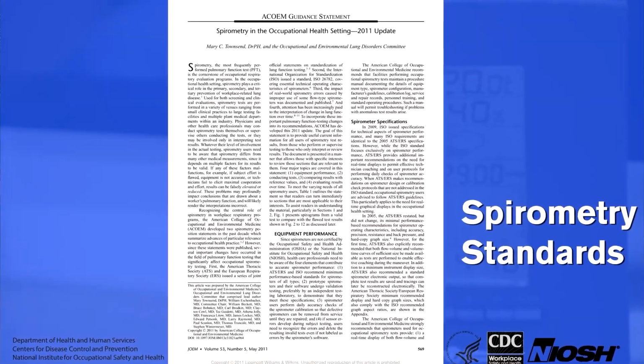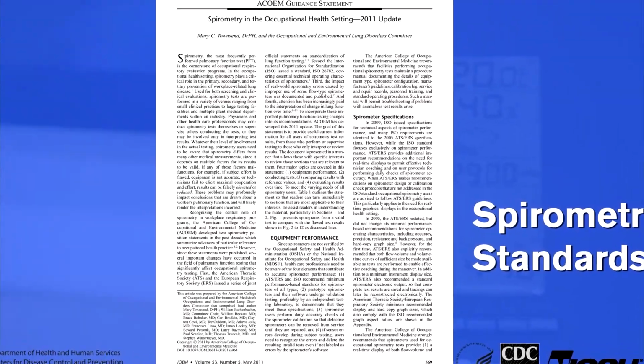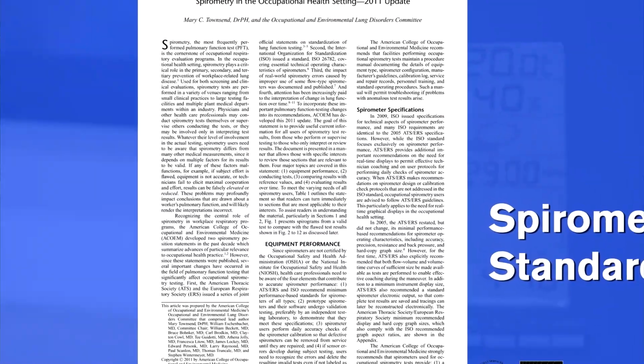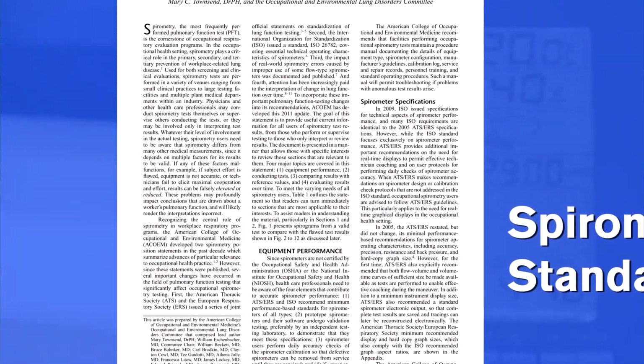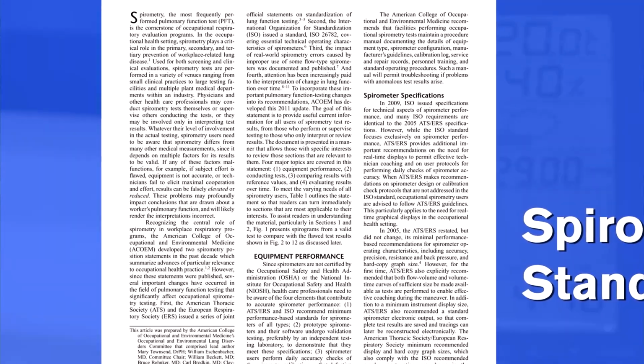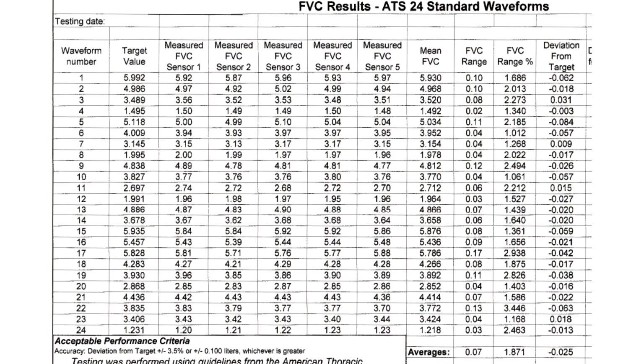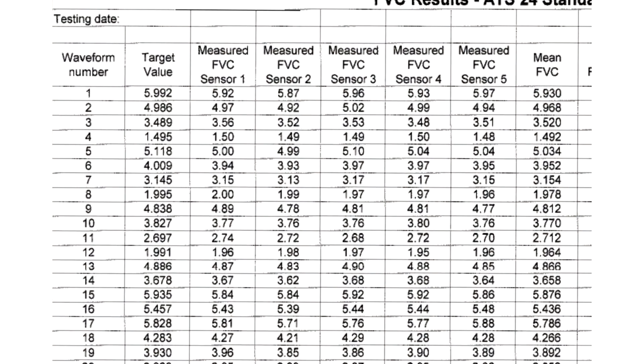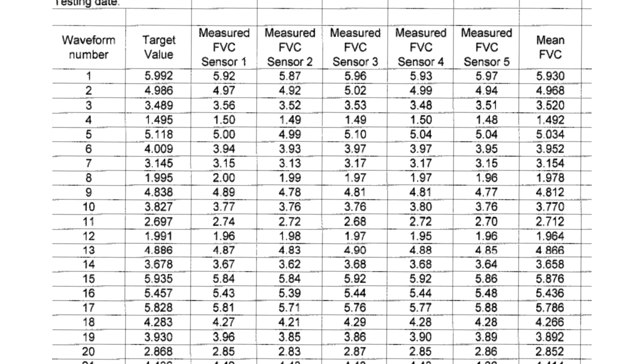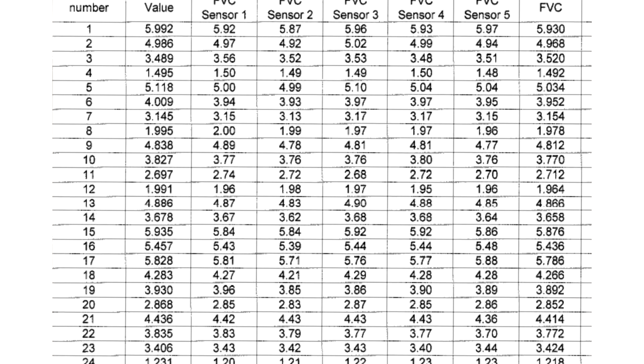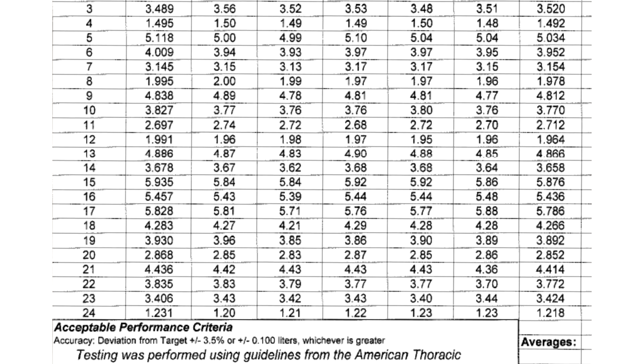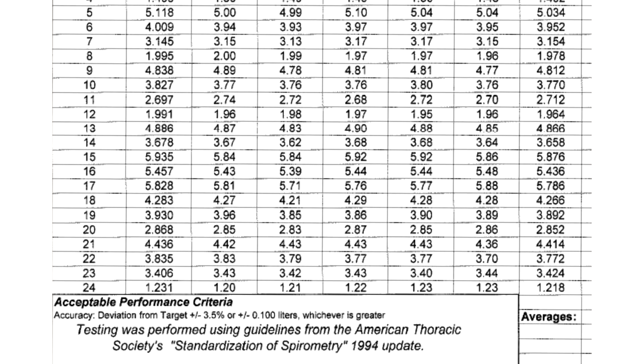The American College of Occupational and Environmental Medicine reiterated the ATS recommendations and recommended additional features for spirometers used in the occupational setting. Every spirometer model should be validated by independent testing prior to manufacturer distribution. This testing uses a waveform generator to produce 24 different simulated spirometry waveforms. You can obtain this certification from the spirometer manufacturer.